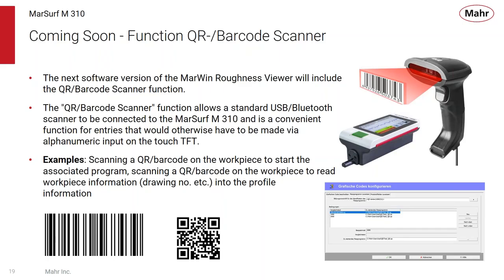Because we have the USB connector on there, one of the things that we can do is program or set up the M310 using a barcode scanner. Envision that a user who may not be that well versed in setting up the M310, even though it is easy to use, can have a barcode as part of the tracking documentation that's coming along with that batch of parts. By simply plugging a barcode scanner into the M310 and scanning the barcode, all the setup parameters, the filters, the trace lengths, etc., can be downloaded into the M310, and now he just has to press the green button and begin making his measurements. This barcode scanner capability is built into the M310 and can be used very easily by the operator.